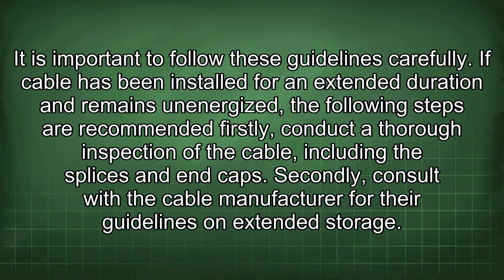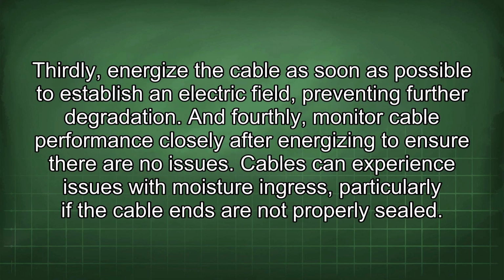Firstly, conduct a thorough inspection of the cable, including the splices and end caps. Secondly, consult with the cable manufacturer for the guidelines on extended storage. Thirdly, energize the cable as soon as possible to establish an electric field, preventing further degradation. And fourthly, monitor cable performance closely after energizing to ensure there are no issues.